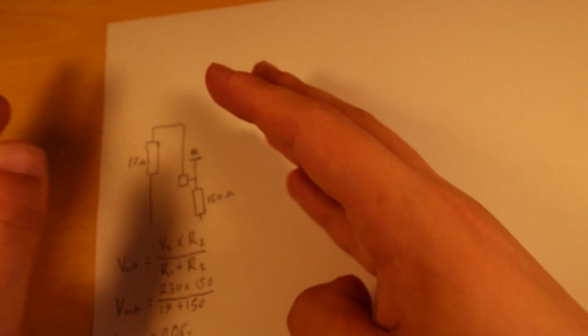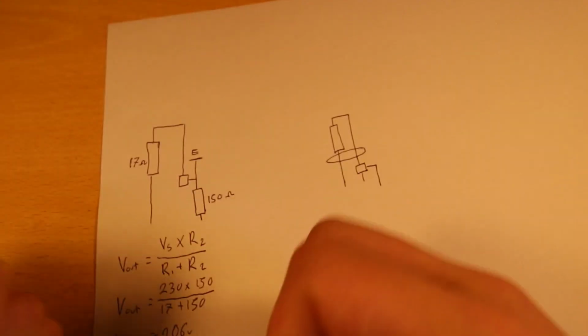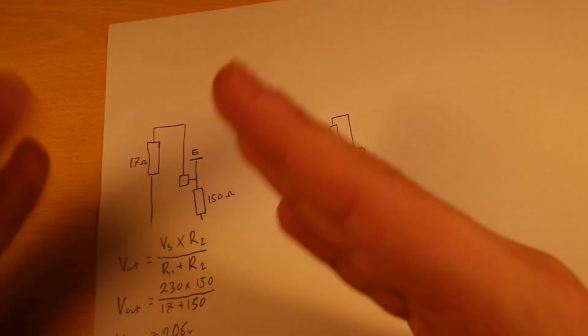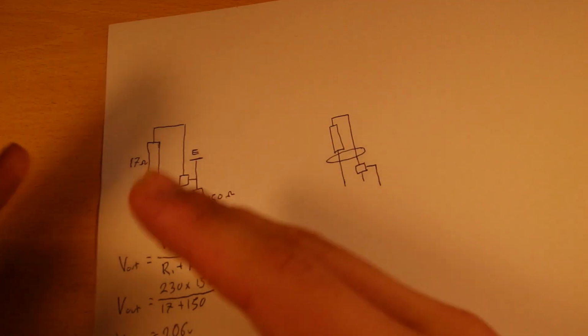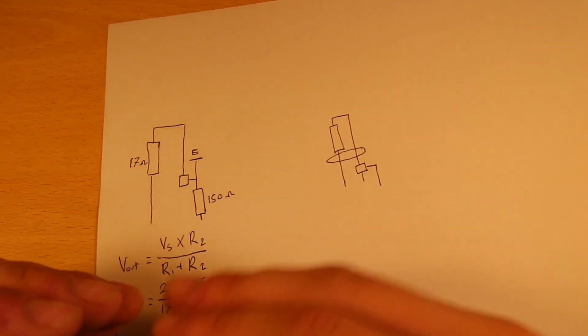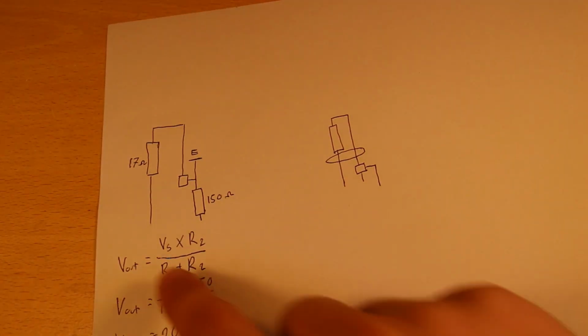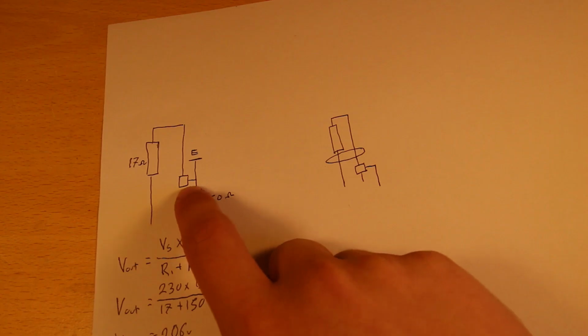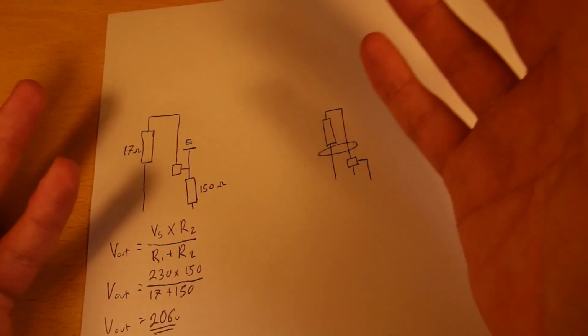Because if, let's say, their neighbour has a TN-C-S earth and they lose their PEN, the earth or the neutral current could divert via a water main or a structural steel part of the building or something like that. It could divert through the load, down through the main earth, into a bonding cable, into some metallic bonded part, down your customer's bonding cable through their main earth, and then back to the substation via their TN-S earth.